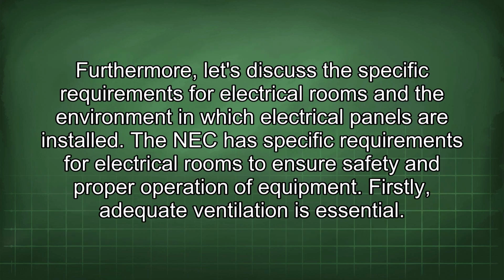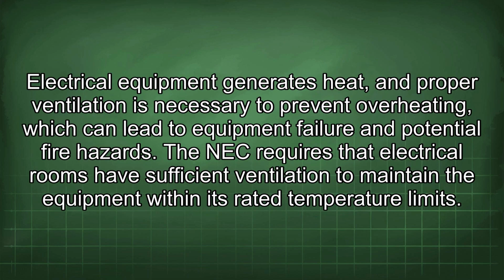Furthermore, let's discuss the specific requirements for electrical rooms and the environment in which electrical panels are installed. The NEC has specific requirements for electrical rooms to ensure safety and proper operation of equipment. Firstly, adequate ventilation is essential. Electrical equipment generates heat, and proper ventilation is necessary to prevent overheating, which can lead to equipment failure and potential fire hazards. The NEC requires that electrical rooms have sufficient ventilation to maintain the equipment within its rated temperature limits.